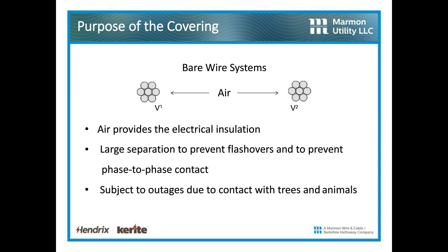If we want to briefly explore the theory of operation, if we take a look at a bare wire system, we use essentially air as the insulation. Air is a halfway decent insulator. But as it turns out, you need a whole bunch of it, so those phase conductors have to be pretty far apart. And that system is still subject to outages due to contact with trees, contact with animals, and conductor clashing, flashover and lightning events.